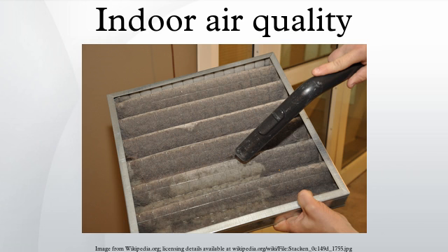HVAC design. Environmentally sustainable design concepts also include aspects related to the commercial and residential heating, ventilation and air conditioning industry. Among several considerations, one of the topics attended to is the issue of indoor air quality throughout the design and construction stages of a building's life. One technique to reduce energy consumption while maintaining adequate air quality is demand-controlled ventilation. Instead of setting throughput at a fixed air replacement rate, carbon dioxide sensors are used to control the rate dynamically, based on the emissions of actual building occupants.